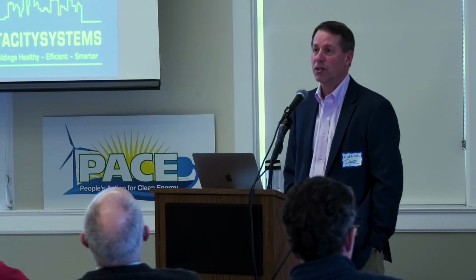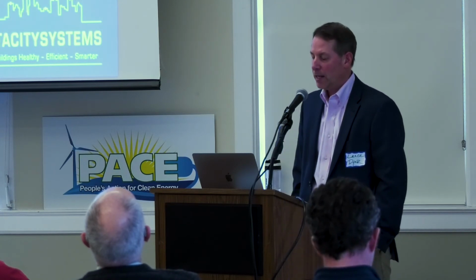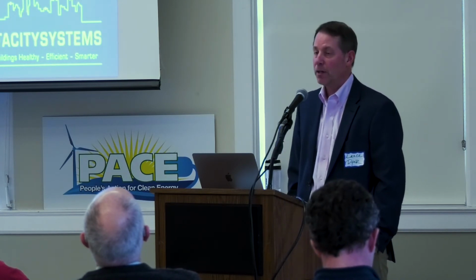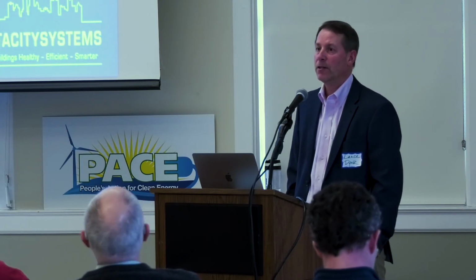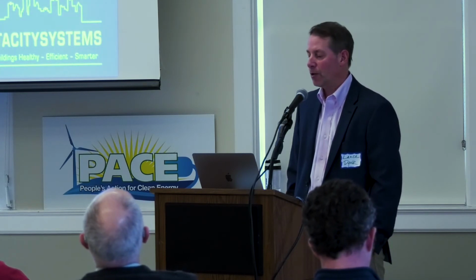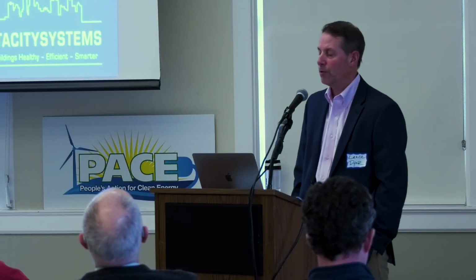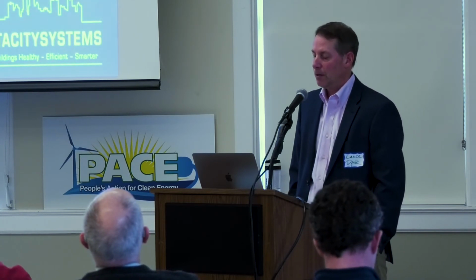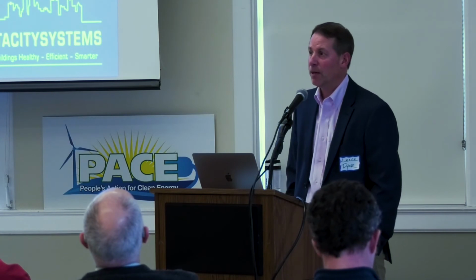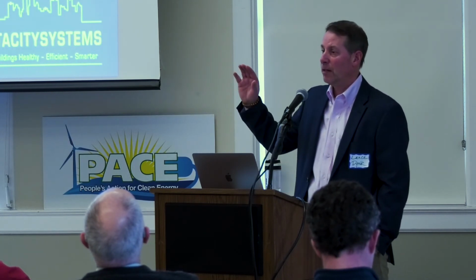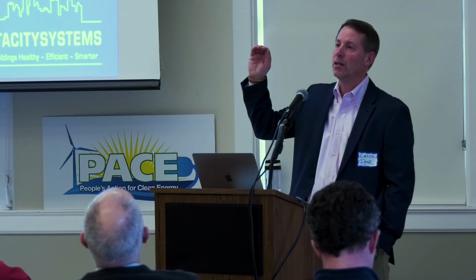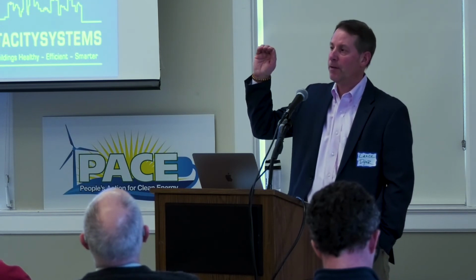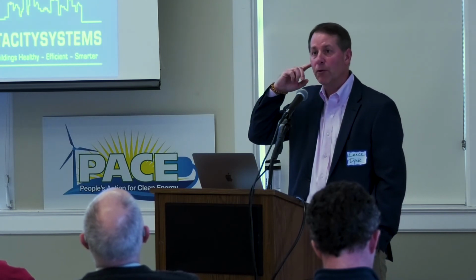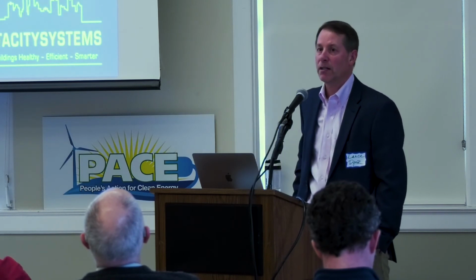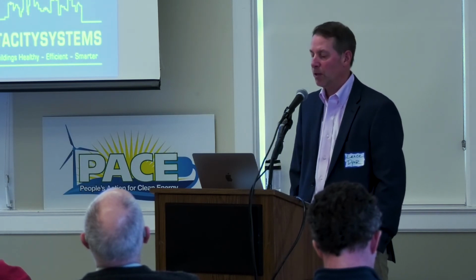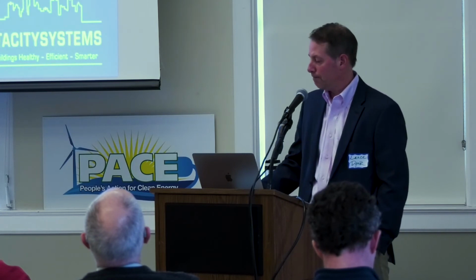What does that mean? Well, in BTUs, it's a lot. You're looking at a difference of more than double in the energy needed for an energy recovery ventilator that's 65% efficient versus one that's 85. That's based on 500 CFM, and a 500 CFM ventilation unit is normally a classroom or library type unit. So if you look at the amount of CFM you need for a classroom and multiply that out, that's quite a bit of BTUs.